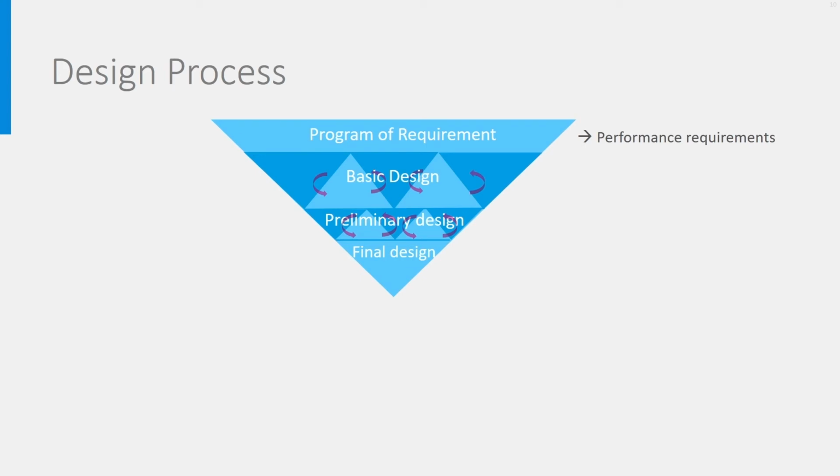As third phase comes the preliminary design, in which the ideas developed in the basic design are worked out to first P&IDs describing how components will interact. Preliminary design values are chosen based on load calculations and estimation of annual energy. This is often based on simulation nowadays. Volume flow rates of air are estimated in order to size the ducts and look how to integrate them in the architectural design. Approximate size of technical rooms are calculated, decisions are made about zones and layout.